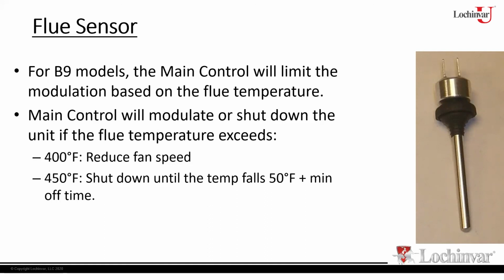Now, if you're seeing this issue and you've got excessive flue temperatures, there's a reason for that. So what's causing that? Well, basically, we're not transferring the heat to the water. So that could be that our V baffles have fallen away from the heat exchanger for some reason. Something's happened there with the V baffles. Could be that the heat exchanger is starting to scale up internally, so I'm not able to transfer the heat to the water properly. That means you just got to go up the stack. Or it could be that the heater is just grossly overfired. So somebody's played with the gas valve when they shouldn't have. We've given it a lot more gas than what it really needs, and we're just overfiring the burner. So there's a few different reasons that would cause that high stack temperature, but obviously it is an issue and we would need to address it.